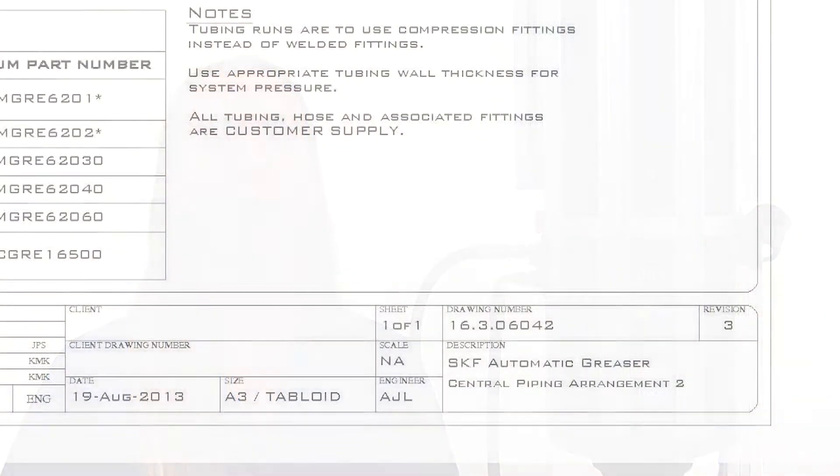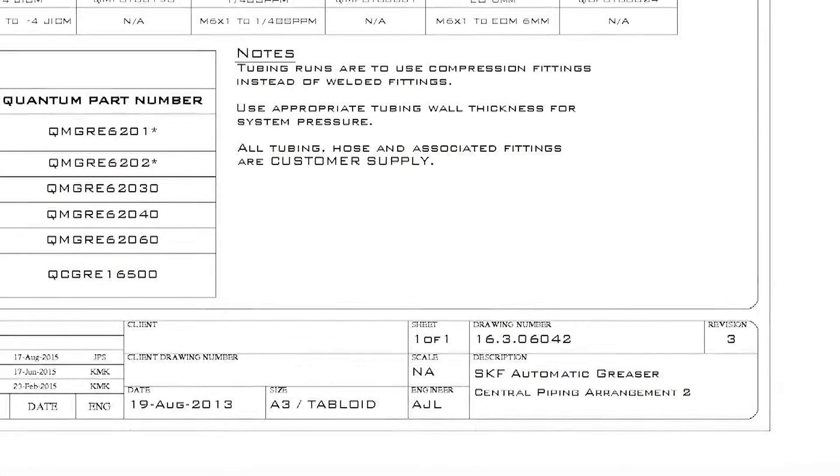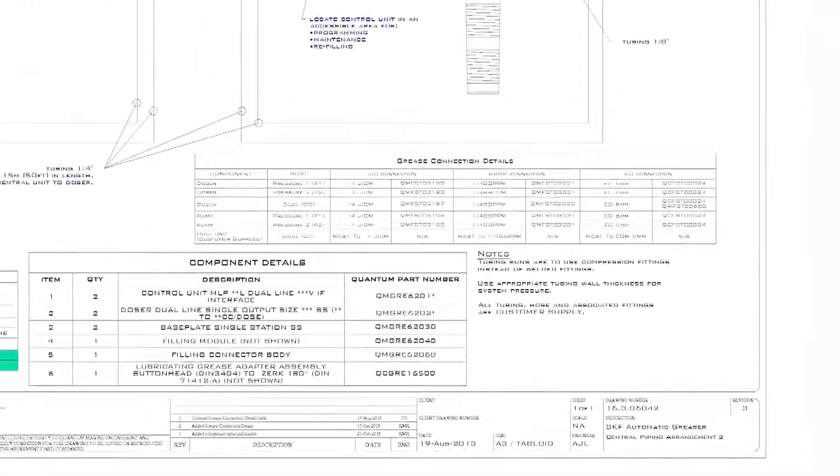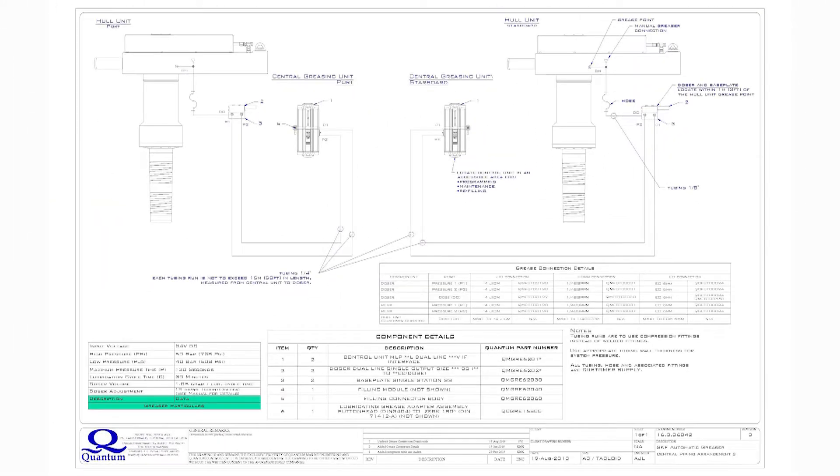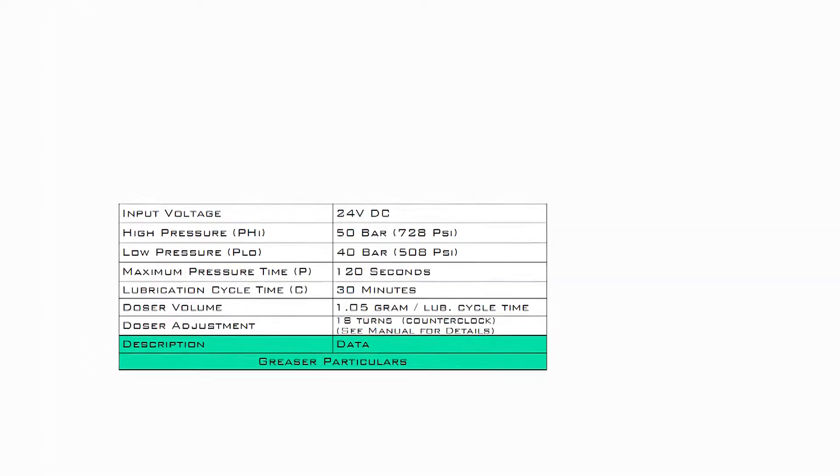Before adjusting any parameters, it is good practice to locate the prescribed set points provided by Quantum's engineering department. If Quantum supplied the automatic greaser for the boat, then you should find an auto-greaser central piping arrangement drawing in the drawing package that Quantum supplied. In this drawing is a table which indicates the auto-greaser parameter set points.